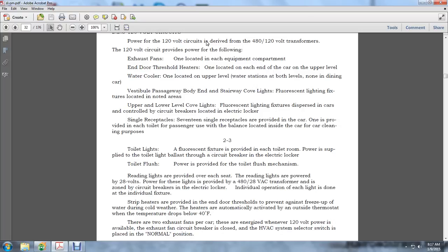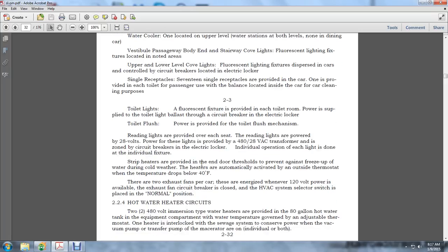A strip heater is provided in the door threshold to protect against freeze-up of the water during cold weather. The heater is automatically activated by an outside thermostat when the temperature drops below 40 degrees Fahrenheit. The two exhaust fans are energized when 120-volt power is available, the exhaust fan circuit breaker is closed, and the HVAC system selector switch is placed in the normal position.